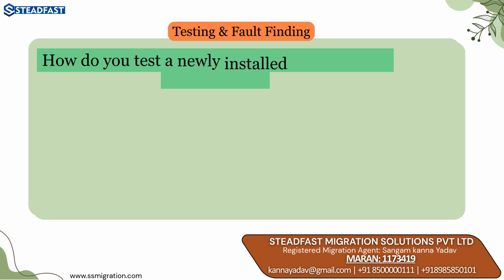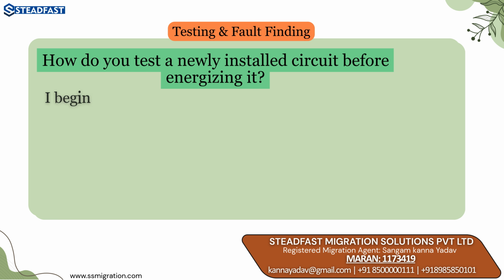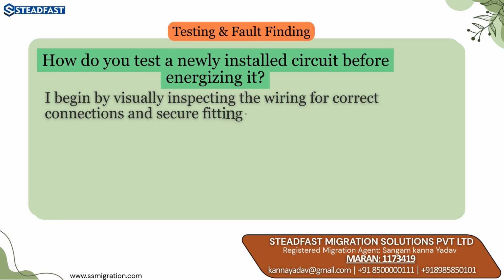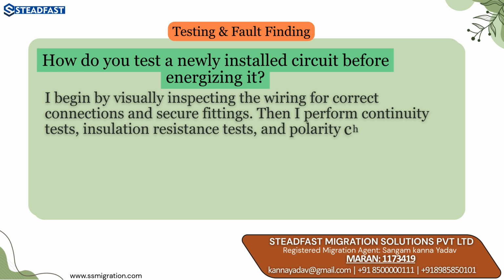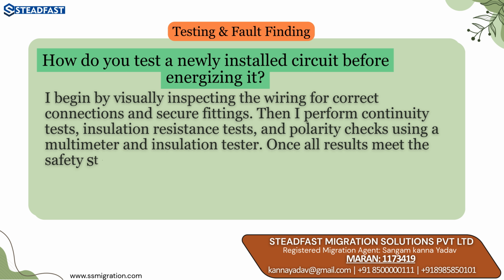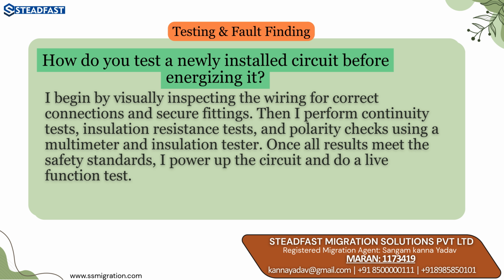Testing and fault finding. How do you test a newly installed circuit before energizing? I begin by visually inspecting the wiring for correct connections and secure fittings. Then I perform continuity tests, insulation resistance tests, and polarity checks using a multimeter and insulation tester. Once all results meet the safety standards, I power up the circuit and do a live function test.